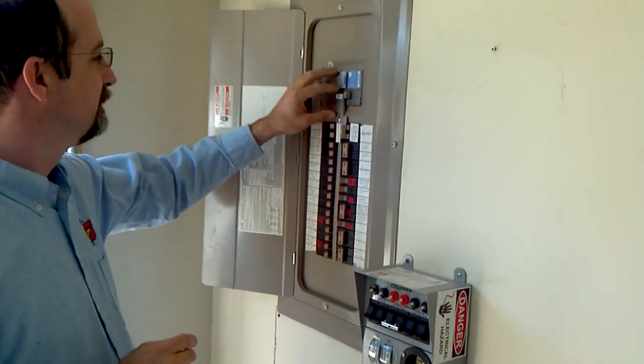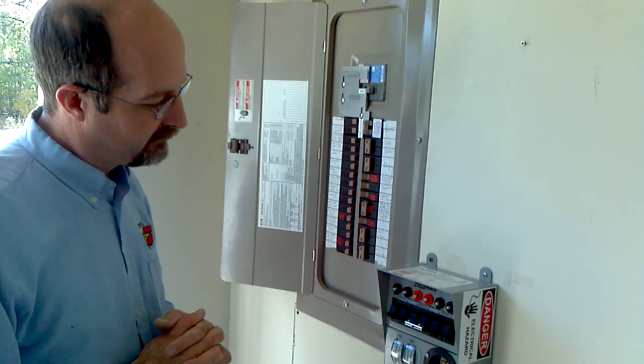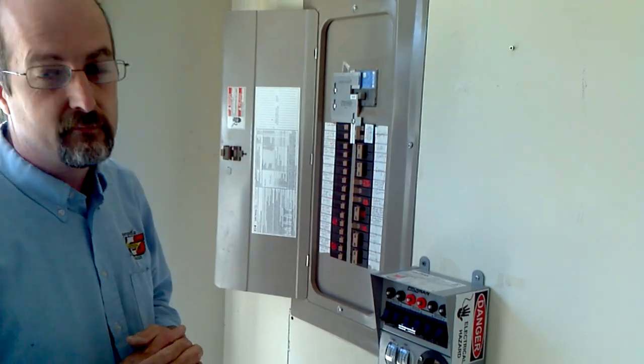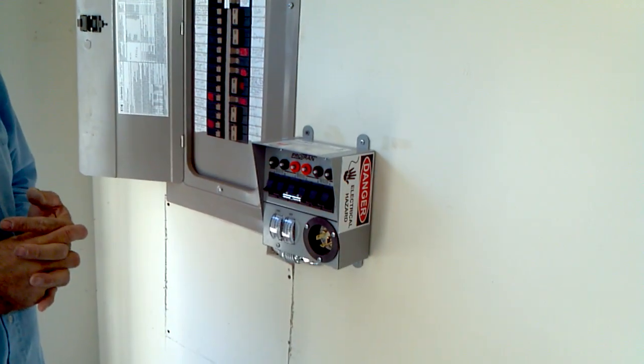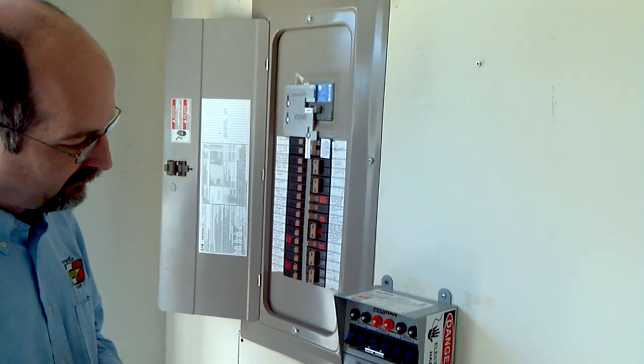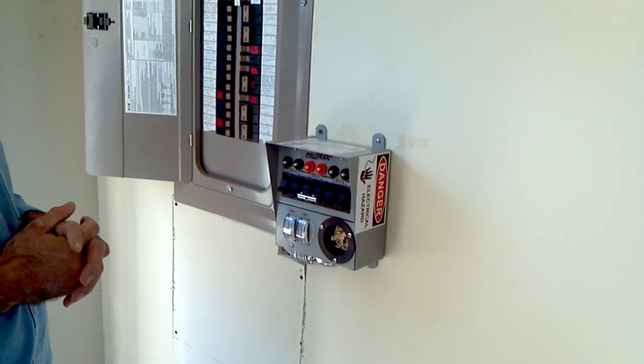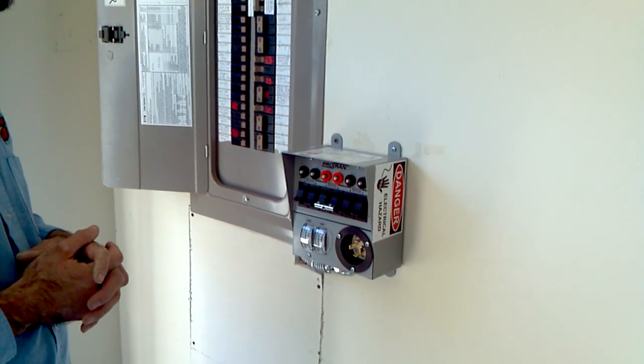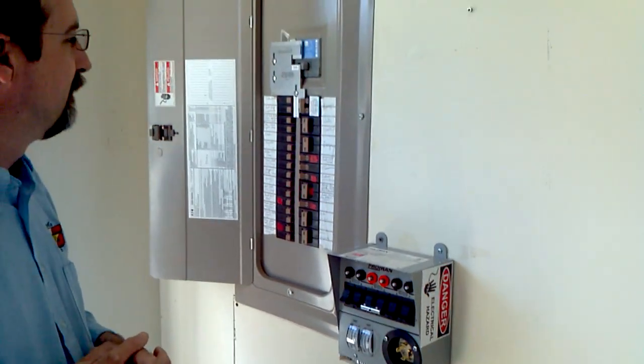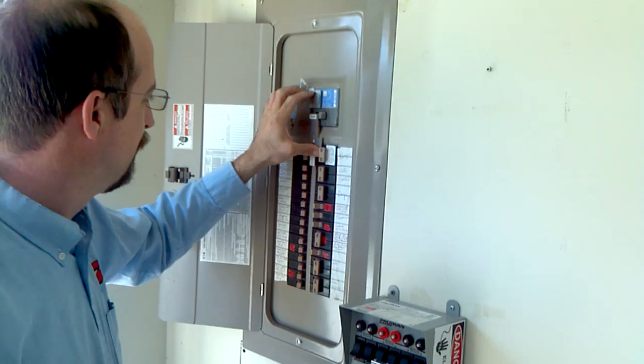That's what we've done. Okay folks, as you can see, we are compliant with NEC codes. We're legal now, and we're not feeding power back into the grid — we're feeding power back into the home. As you can see right there, there's a transfer switch working alongside an interlock kit. The transfer switch will allow non-electrical personnel to simply come in and flip a switch for emergency power, and for people that really know about it, to power on the entire house.